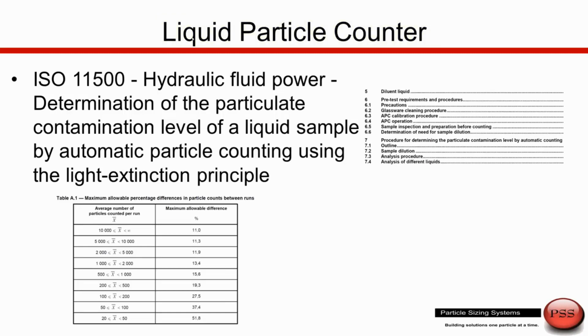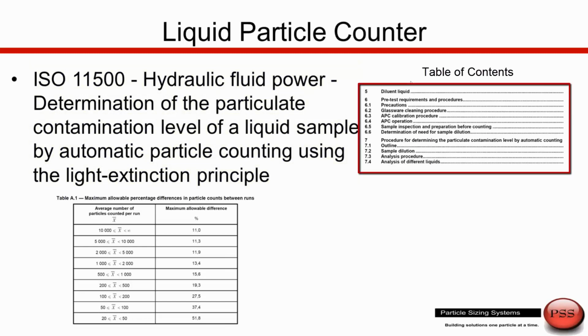And these standards can include the ISO standard for liquid particle counters, which is ISO 11500, hydraulic fluid power, using particle counters to make these kinds of measurements. What you see on the right is just part of the table of contents of the topics addressed in this particular standard, which include how do you clean the glassware, how do we do the calibration, how to make sure the instrument is ready for use, how might we deal with dilution, and also some other analysis procedures.